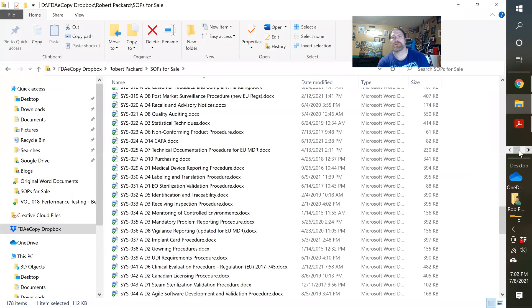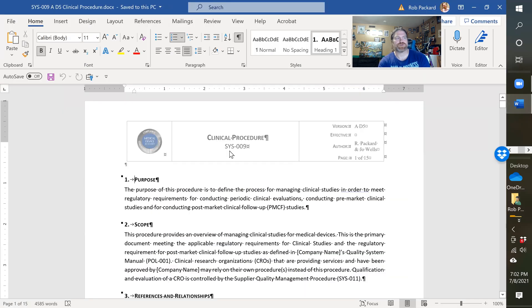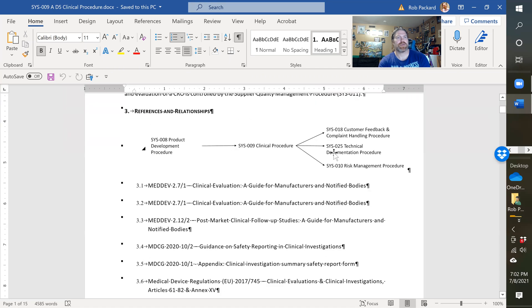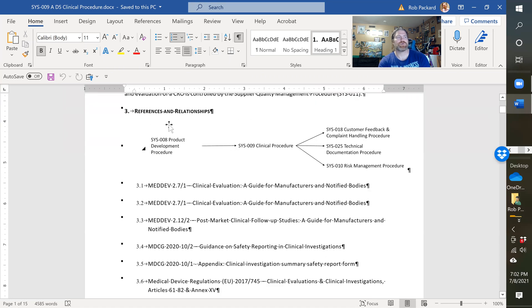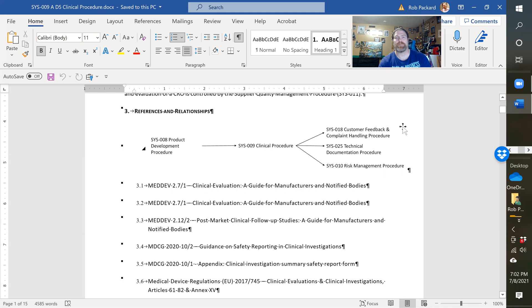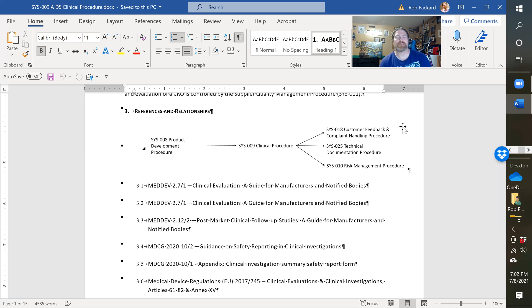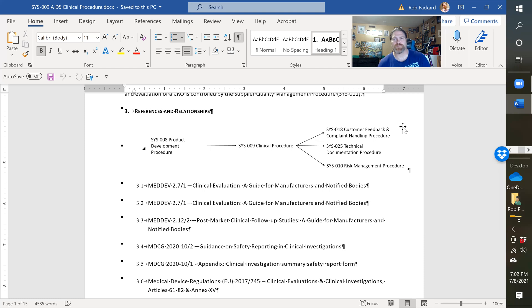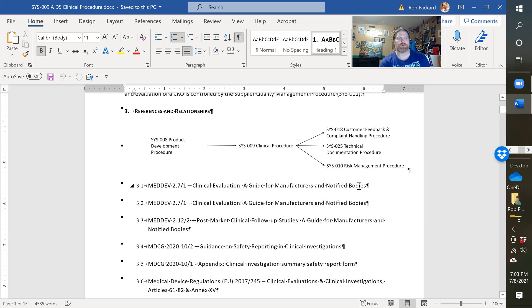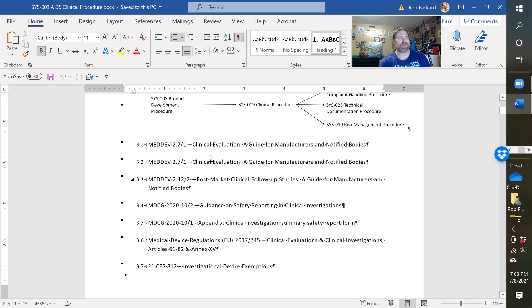The third document we have here is the actual procedure. Here's SYS-009, also a 15-page procedure. It shows you the product development procedure would be an input to the process, and the output would be your complaint handling and customer feedback. Any things that occur in your clinical study might be put into your complaint handling procedure. It would also become part of your technical documentation and risk management procedure, as clinical studies are a validation activity.